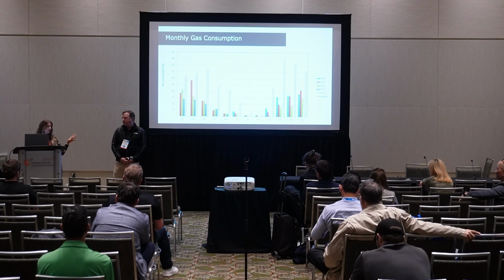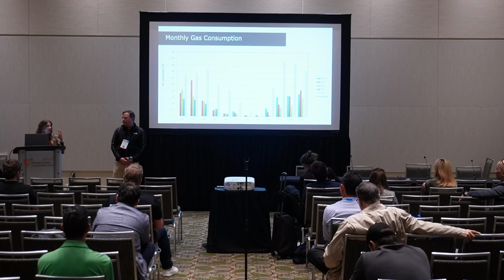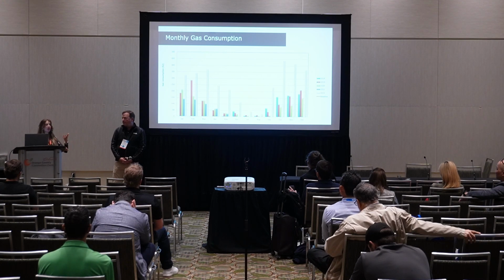There's definitely still scenarios where it makes sense to put that in, but the other way you can get the data is from a building automation system. It's called virtual metering, so basically I know my temperature in, my temperature out, I know my flow, I can calculate my BTUs of that system. Or I know my amperage, so I can calculate how much energy that's using.